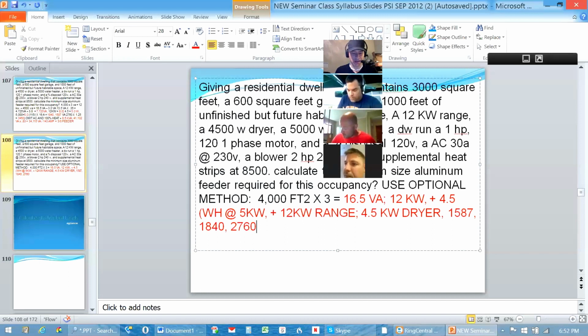That's the other thing that's kind of different here. If you look to the right-hand column up at the very top of the next column of the page there, you'll see section C, but section C is a separate step. So write yourself a note at the bottom left-hand column of page 73 that you want to stop after you're done with the motor loads under section 4, B4, and then draw an arrow up to the top of the paragraph where it gives you your D rating values listed under B right there at the very top where we were at.